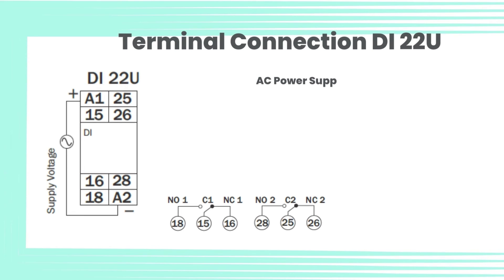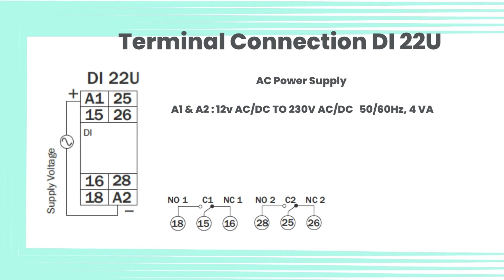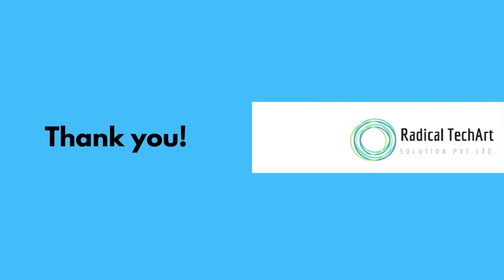Terminal connection DI22U. AC power supply: A1 and A2, 12V AC/DC to 230V AC/DC, 50/60 Hz, 4 VA. Relay terminals: NO1-18, C1-15, NC1-16. NO2-28, C2-25, NC2-26.